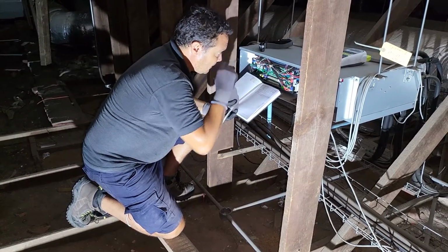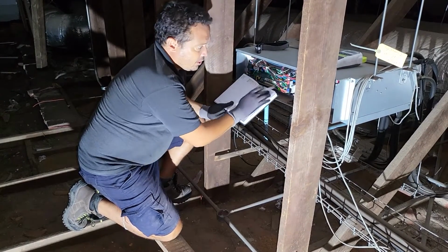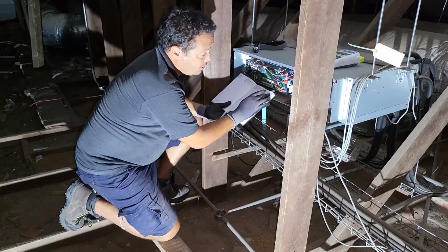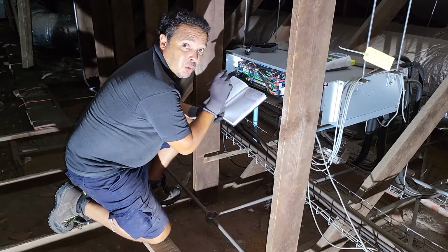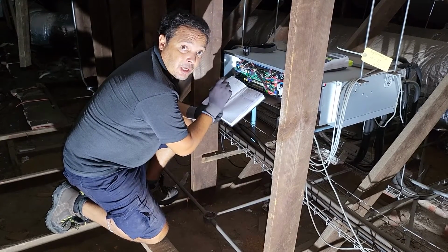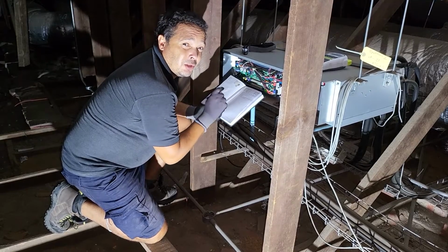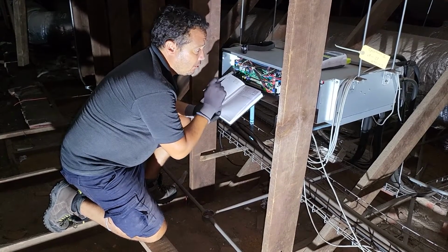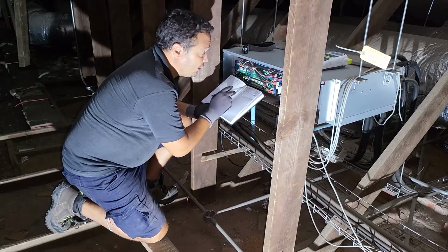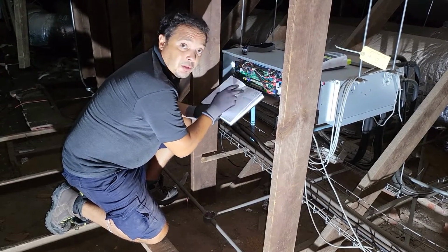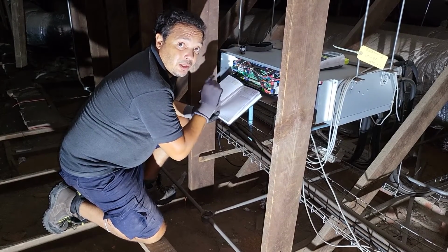According to the 215 error code, which is showing at this MCU, you can actually see here it says E-215, which means it's more than likely that duplicate addressing exists on this MCU and one of the others. But just to be thorough, we're going to go through each one of these MCUs, document exactly which addressing it has and the position of the dip switches, and then see if there are any duplicates, and how we're going to rectify it.